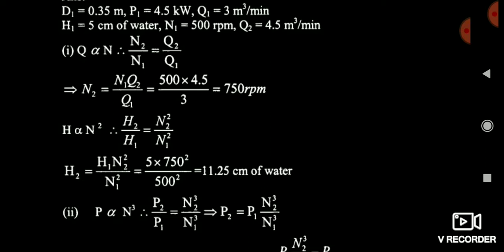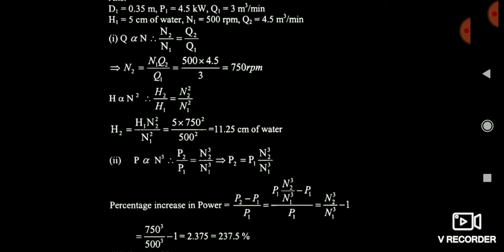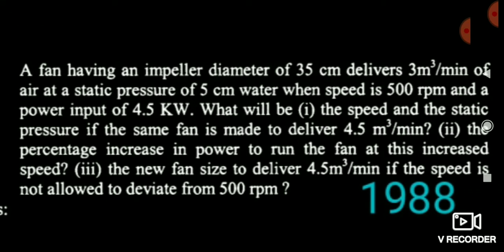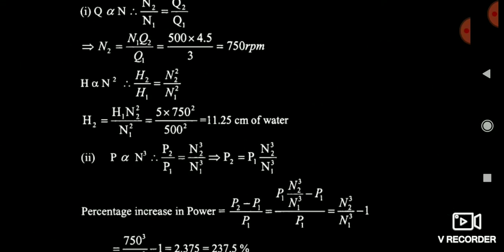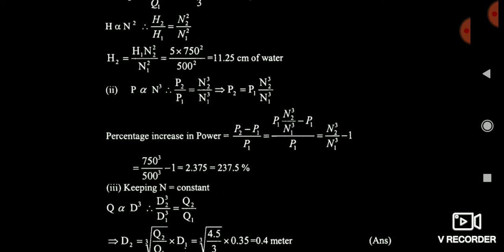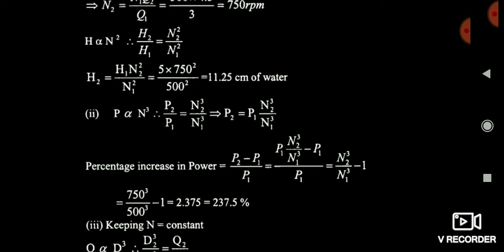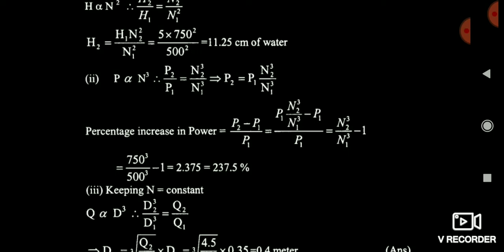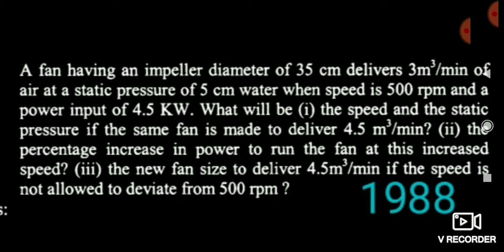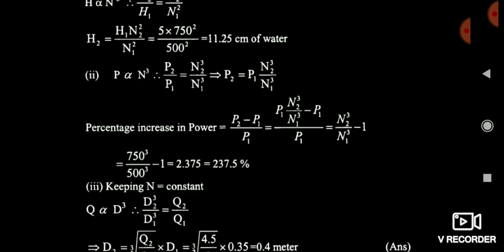After that, since head is proportional to the square of speed, using H2/H1 = N2²/N1² we get H2 = 11.25 cm of water. For the second part, it asks the percentage increase in power. Using P2/P1 = N2³/N1³ with P1 = 4.5 kW, and cancelling P1, we get the answer: 237.5 percent increase.